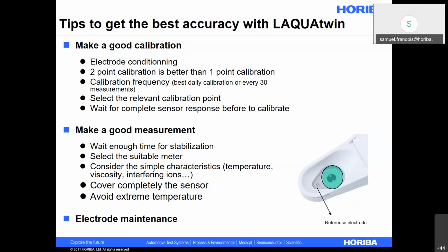Also, we want to make a good measurement, so for this, we wait enough time to do the stabilization. We need to select the suitable meter. So, for example, sodium or salt, but it can also apply for the other bench handle meter. Consider the sample characteristics. What is the temperature? Is it a viscous sample? Are there any interfering ions in my sample?